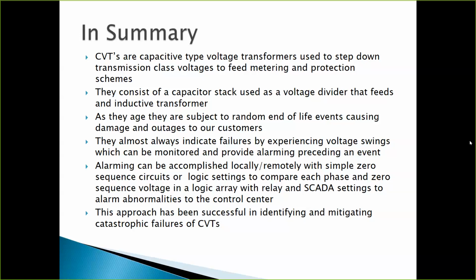Some of you use built-in capacitive voltage transformer supervision. I'm not sure what built-in capacitive voltage transformer supervision elements provide to detect the voltage. He might be referring to built-in CVT. Oh, built-in. So we use predominantly SEL relays, okay, and those relays you can configure the settings. The settings are actual settings that we developed and deployed to the relays, and it does the math for you, but also there's a zero sequence, what you call a pre-packaged design or setting in the relay itself for zero sequence, and I don't exactly remember how they do that.